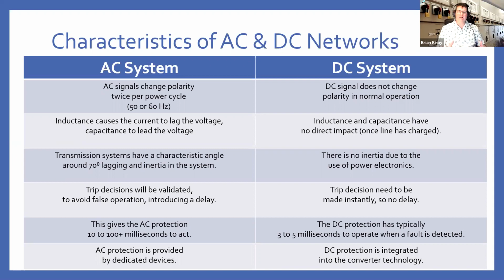AC networks, 10 to 100 milliseconds or even longer, maybe at sort of low voltage distribution, you may have several hundred milliseconds to act before any serious damage is done to your network. DC protection, typically you have single figure milliseconds in order to operate. As a result, DC protection tends to be a fire first, ask questions later approach.